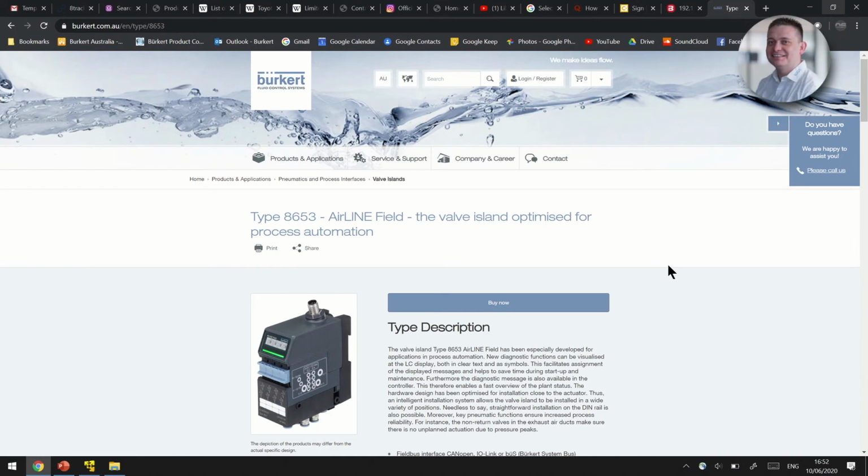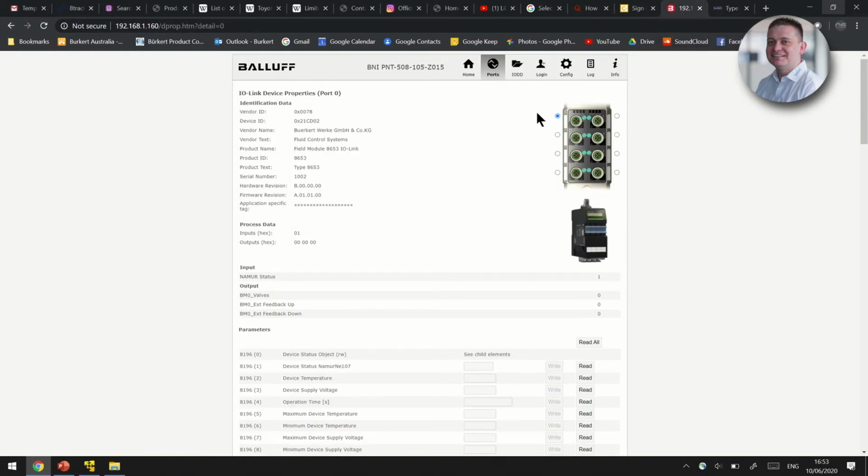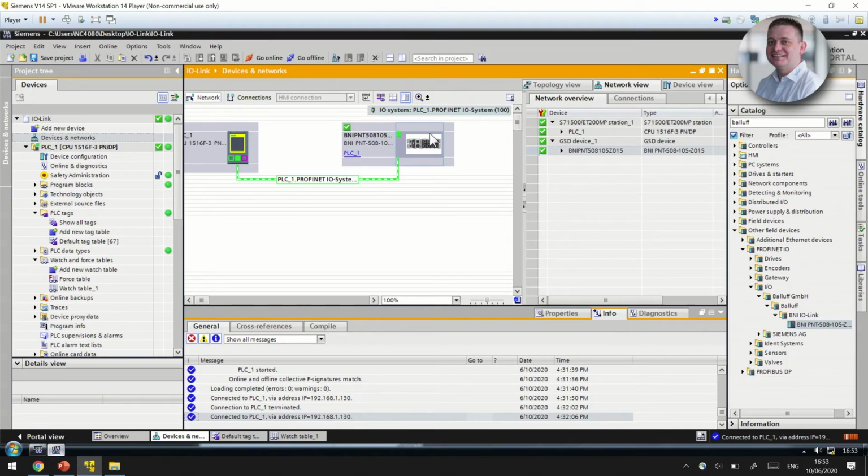Thanks, Chris. We're going to take a look at the Bürkert 8653 IO-Link remote valve manifold, and how that's integrated into a Profinet master. We first need to download the IO-Link description files. You can find these on the Bürkert website under device description files. Once downloaded, we need to configure them into the IO-Link master. In this case, we're using a Profinet IO-Link master from Balluff. Ports are configured as port number 1, and then what we do in TIA Portal is import that block as an element in the Profinet system.